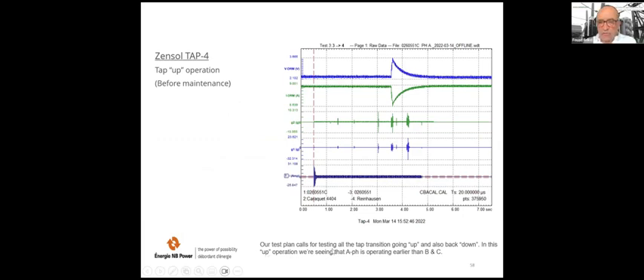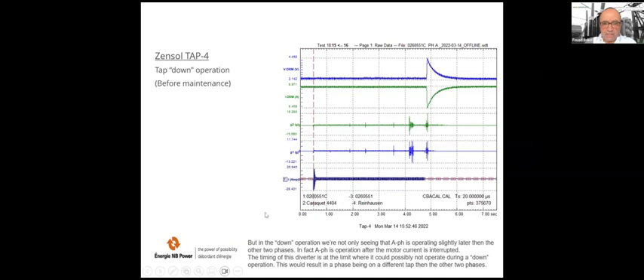Our test plan calls for testing all the tap transitions going up and also back down. In this up operation, we're seeing that A phase is operating earlier than B and C. I hope that it's clear here. But in the down operation, we are not only seeing that A phase is operating slightly later than the other two phases. In fact, A phase is operating after the motor current is interrupted. The timing of this diverter is at the limit where it could possibly not operate during a down operation, and this would result in a phase being on a different tap than the other two phases.